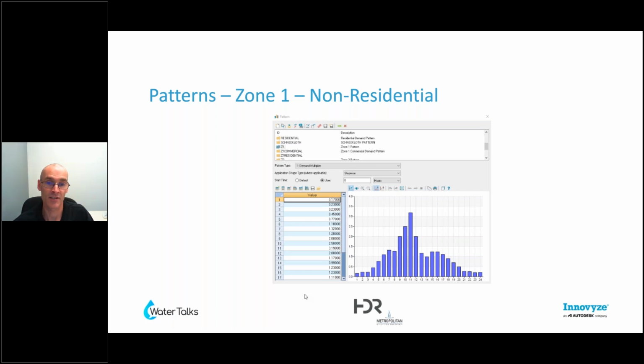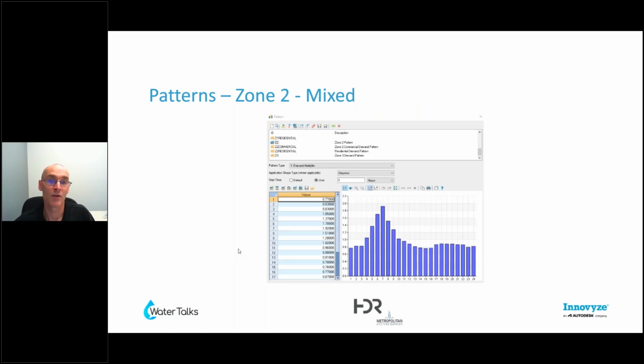The other interesting thing here is their 3 zones act so differently, just simply because zone 1 here is a primarily non-residential zone with commercial and industrial, so it comes up in the morning and subsides in the afternoon with that midday peak that you'd expect. And then as we move to zone 2, it's more mixed, so you can start to see this residential irrigation influence in the morning, and then it comes down and you get that secondary normal diurnal pattern.